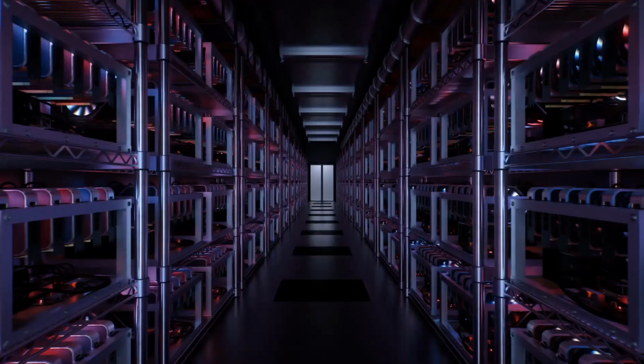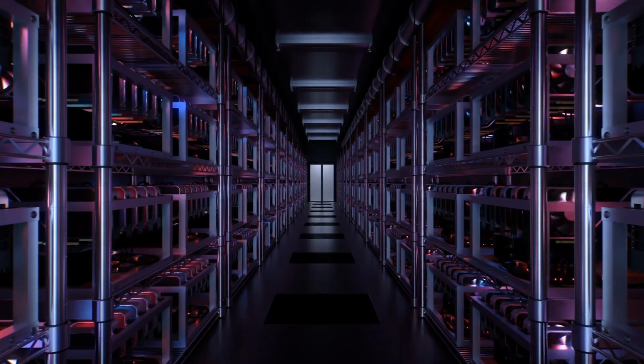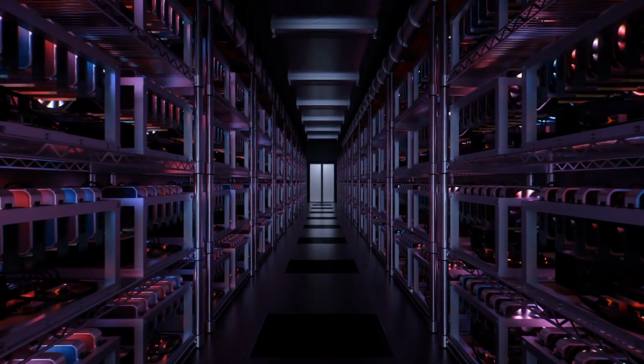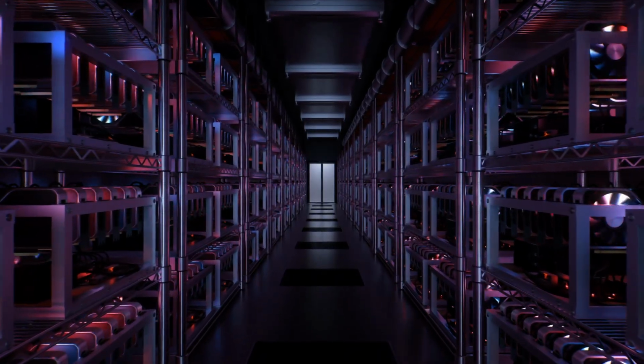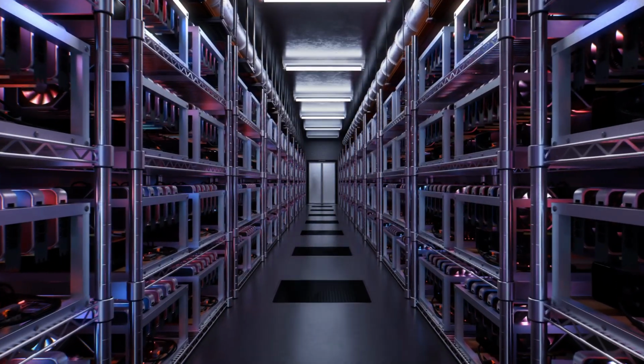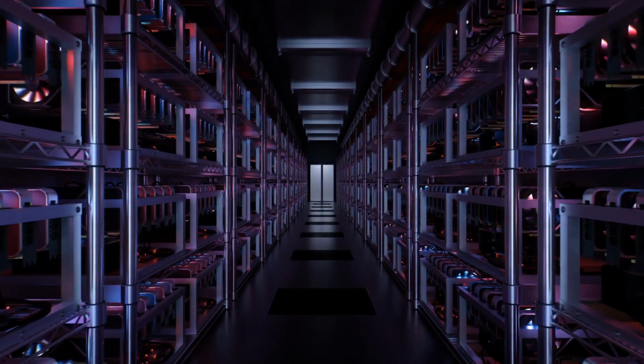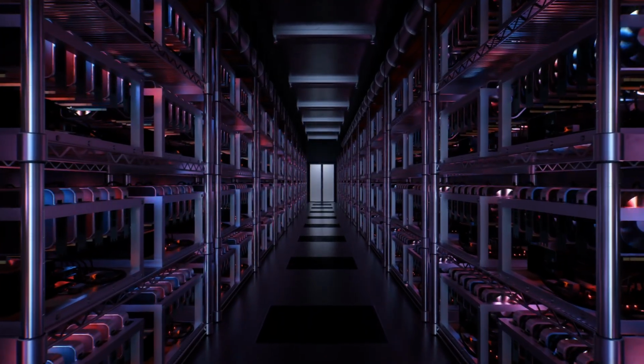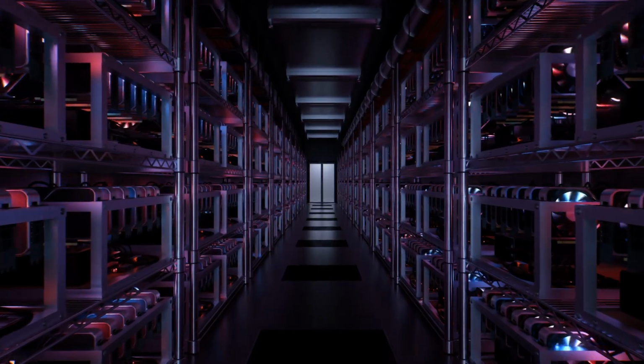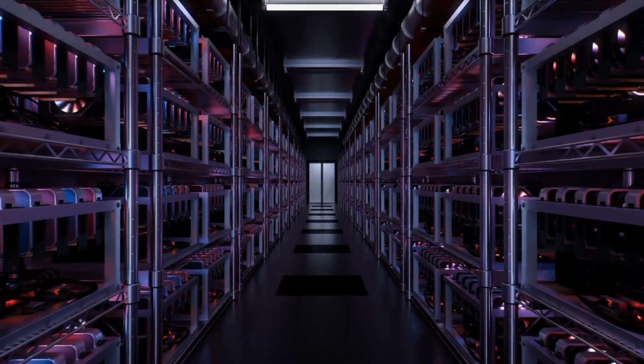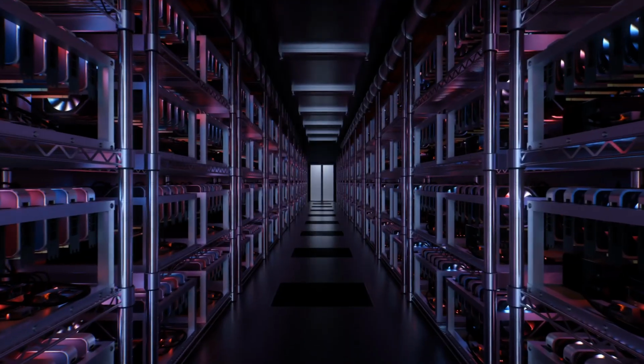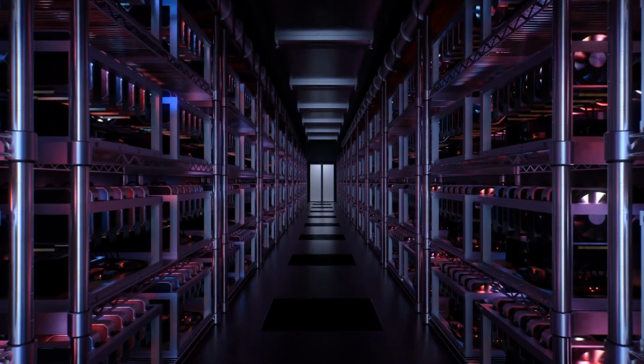Ah, right. Trying to move a megawatt of heat with traditional CRAC air conditioning units would require hundreds of kilowatts of fan and compressor power. By switching to liquid, you slash the facility overhead. You push the PUE down dramatically, moving it toward 1.1 or 1.2. You are literally shaving massive amounts of wasted power off the top of the facility's requirements.